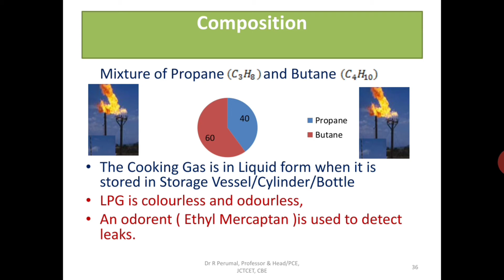So how is LPG stored? The gas is stored in liquid form. While storing the liquid LPG in a cylinder, it is filled up to 85% of its total volume. The remaining 15% is provided as empty space. Once the liquid is filled in the cylinder, the liquid starts to vaporize and this vapor occupies the 15% empty space. Then this vapor creates certain pressure inside the cylinder and maintains the LPG in the liquid state. So this is the storage of LPG.